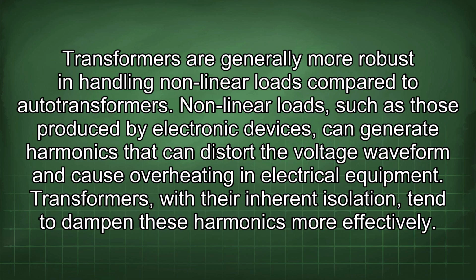Transformers are generally more robust in handling nonlinear loads compared to autotransformers. Nonlinear loads, such as those produced by electronic devices, can generate harmonics that can distort the voltage waveform and cause overheating in electrical equipment. Transformers, with their inherent isolation, tend to dampen these harmonics more effectively.